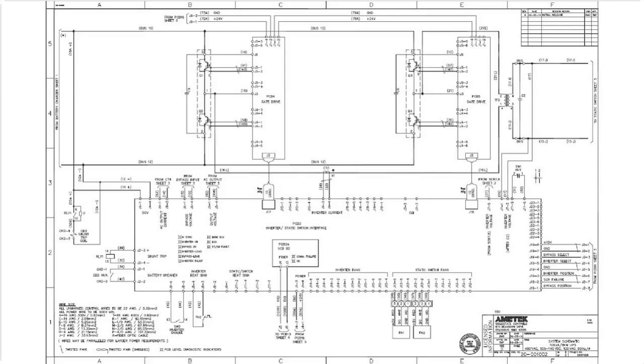Remember I said that we trip the battery at 105 volts. This is what this circuit here is doing on this control board, and it makes this relay 1 close and shunt trips the battery input breaker there. Very similar to the micro SE UPS. This is an indicator only on the DC input breaker. It tells us whether the battery input breaker is closed or not. Okay. This is the inverter enable switch, switch 2, which is that rotary switch on the front of the UPS that turns the inverter on and off.